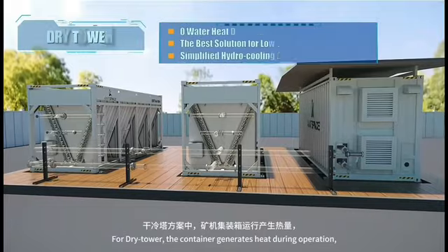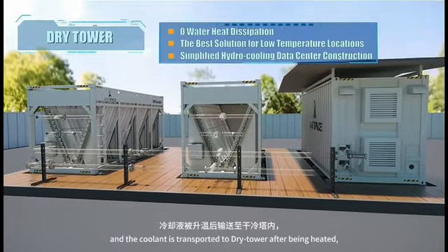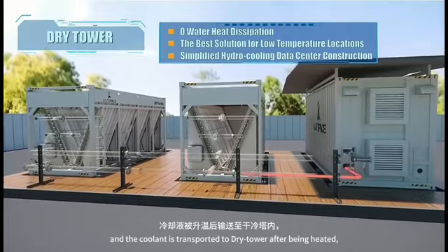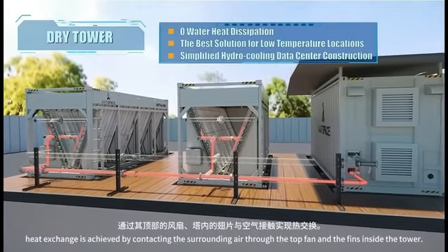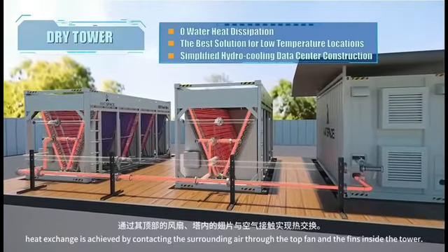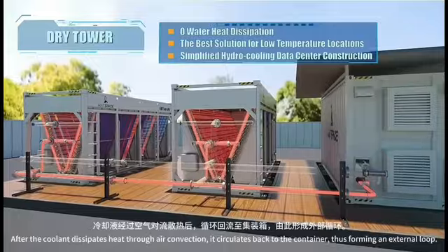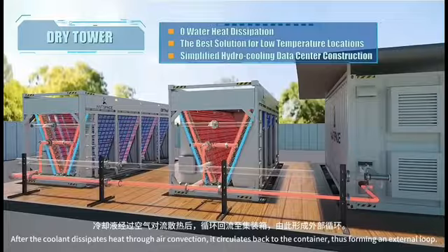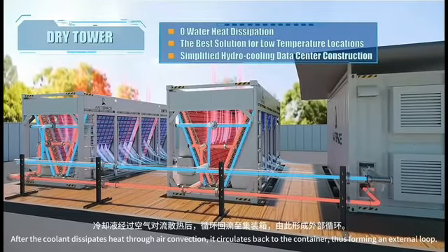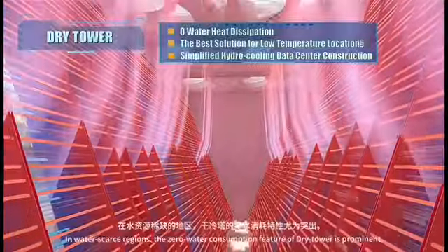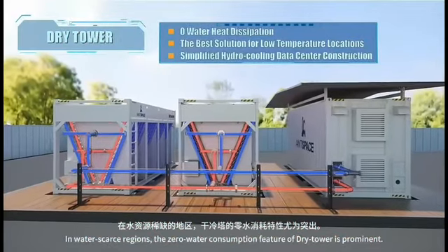For dry tower, the container generates heat during operation, and the coolant is transported to the dry tower after being heated. Heat exchange is achieved by contacting the surrounding air through the top fan and the fins inside the tower. After the coolant dissipates heat through air convection, it circulates back to the container, thus forming an external loop. In water-scarce regions, the zero water consumption feature of dry tower is prominent.